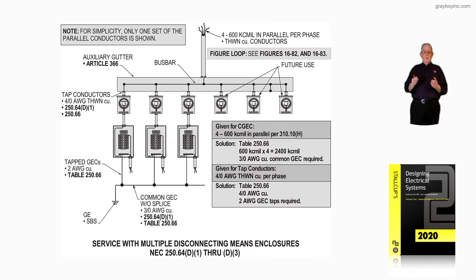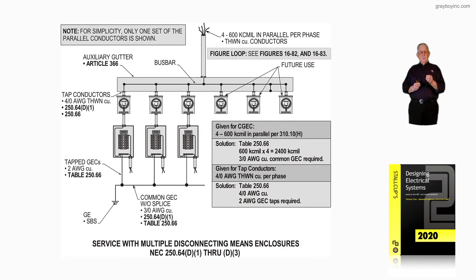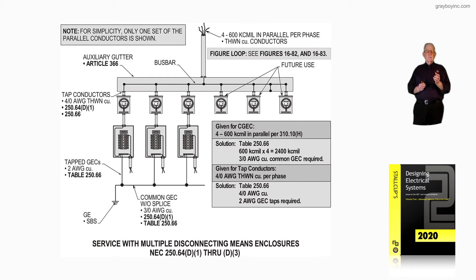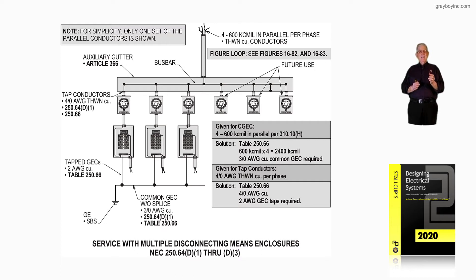The 3/0 AWG requirement is found when you read through 250.64(D1) through (D3). So the common grounding electrode conductor, as shown in callout, is 3/0 AWG copper per 250.64(D1) and table 250.66. For the tap conductors, if they were 4/0 AWG conductors feeding that main, the grounded conductor for an effective ground fault path would be a number 2 per table 250.102(C1). The grounding electrode conductor would also be number 2 per table 250.66, based on those 4/0 AWG conductors tapped from the auxiliary gutter to the main and the panelboard.